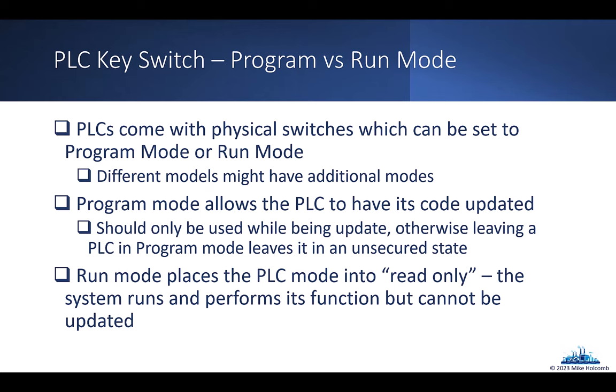Or if you have the little dip switches, it's not as secure, right, to determine whether somebody has locked a PLC or not. So what you have to do is have somebody physically walk and check PLCs from time to time to see if that switch is in run mode. Or there are some platforms, like the Dragos platform, that have the ability to check certain PLCs remotely, just a query to see, hey, are you in run mode or are you in program mode?